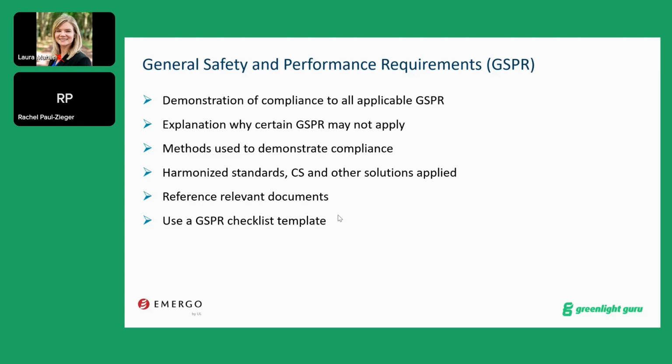You need to provide the methods used to demonstrate compliance. So it means testing reports, clinical evaluation report, usability engineering file. You need to define the harmonized standards, common specification, and other solutions you applied. So for doing this, obviously, you need to have defined what the harmonized standards are, if there are common specifications. And you need to provide the reference of the relevant document. So you need to be very precise about what the reports are and where they are located.